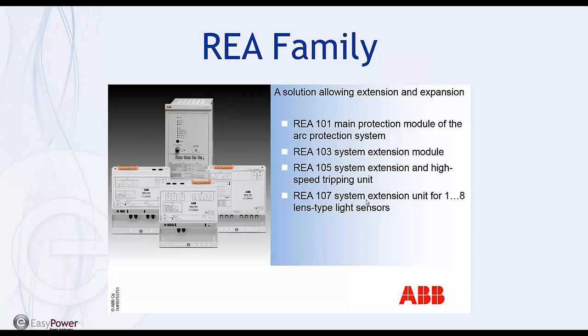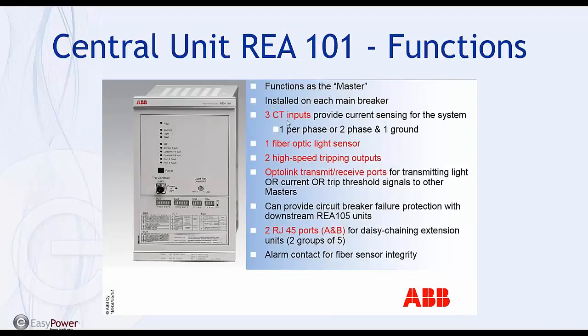Here's the main unit. It functions as the master. It has the CT input, so you can either have two-phase, three-phase, or two-phase and ground. You can use a zero sequence CT or residual. You have one fiber optic loop sensor. You have two high-speed tripping outputs. You also have a third output that's standard. You can use those for breaker failure as well. You have an opto link that connects the two to transmit and receive current information or trip information or light. We already talked about breaker failure protection, and you can connect them to the extension units via RJ45. You connect up to two groups of 5 extension units.